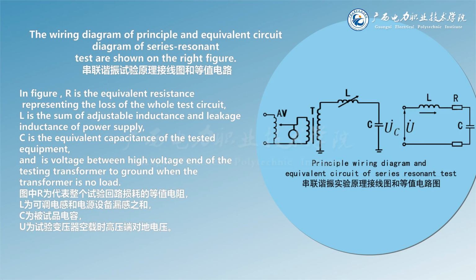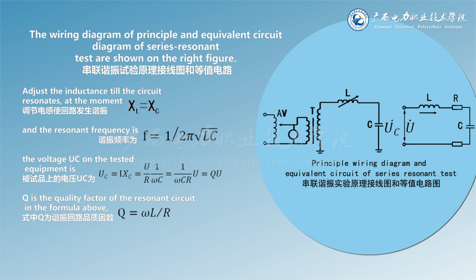In the figure, R is the equivalent resistance representing the loss of the whole test circuit, L is the sum of adjustable inductance and leakage inductance of the power supply, C is the equivalent capacitance of the tested equipment, and U is the voltage between the high voltage end of the testing transformer and ground when the transformer is no load. Adjust the inductance until the circuit resonates. At the moment XL equals XC, and the resonant frequency is as shown. The voltage UC on the tested equipment is as shown, where Q is the quality factor of the resonant circuit in the formula above.